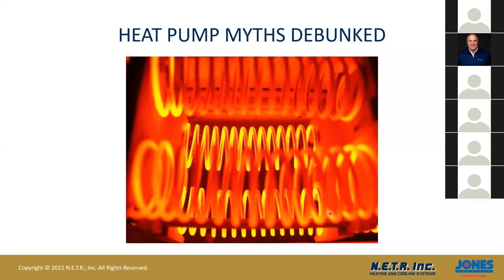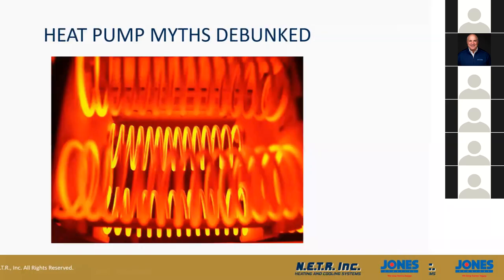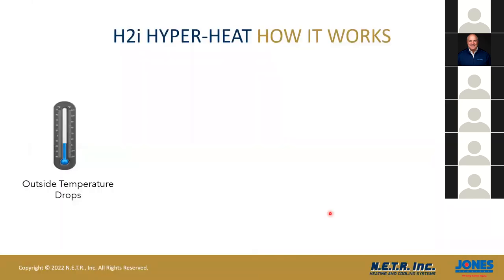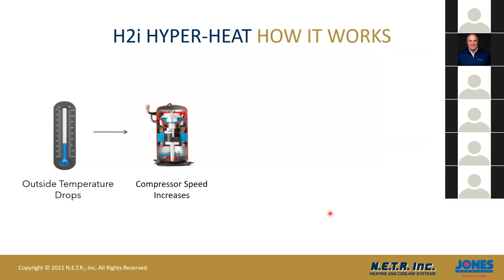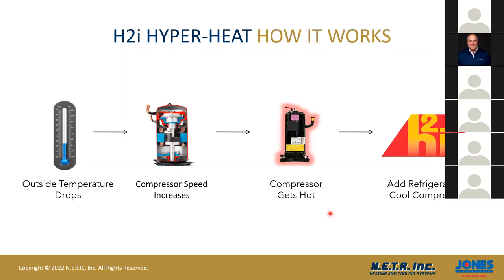If we look back at that slide, at that $53 per million BTUs, there's your cost. Most hyperheat systems do not have backup electric heat in them. You can have backup electric heat put in them, but I don't think you would ever use it on cold days. Very, very rarely. So how does hyperheat work? How do these systems work? When the outdoor temperature drops, the compressor speed increases, the compressor gets hot, we add refrigerant to the compressor, and then we take that heat and we use it inside of your home at that point. So we're heating your home with basically the speed from the compressor and the outdoor air that's coming over the refrigerant and using it inside of the home.